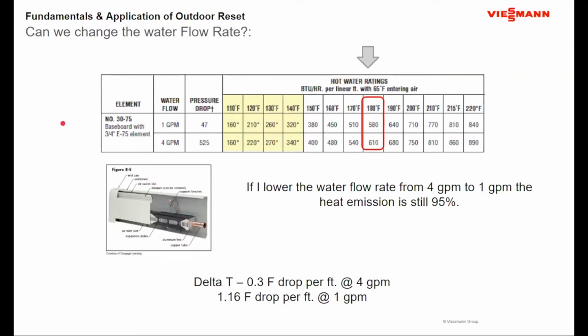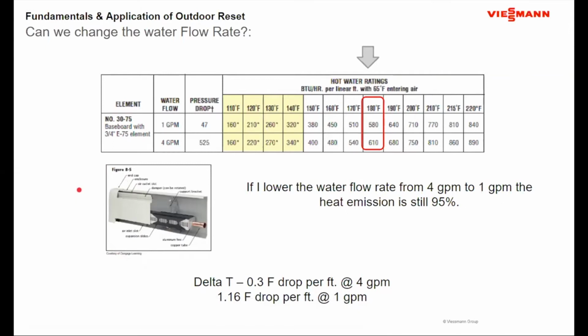All of a sudden, if I have a series loop and a long run with a lot of baseboard, the performance concern comes out, where I'm worried about how much BTU per linear foot is coming out of the baseboard at the end of the run versus the front end of the run. So when somebody says, well, what about varying the flow rate? With baseboard, it becomes very difficult to adequately control the heat transfer purely by changing the flow rate, and also to get consistent performance through all combinations of flow rates at both ends of the baseboard runs.